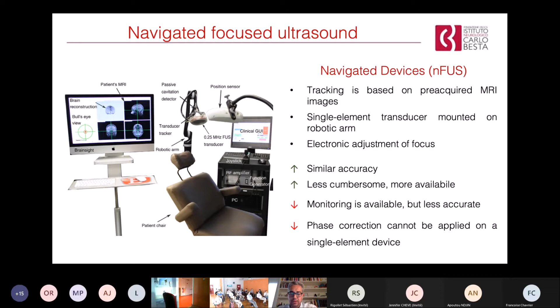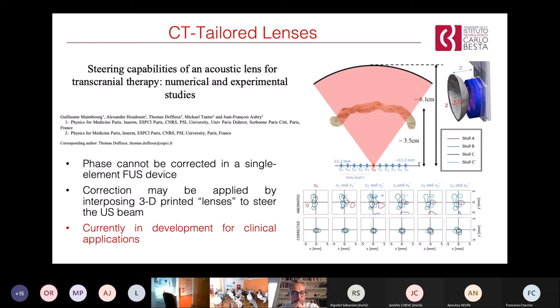There are acoustic lenses that are under development. They are built, again, on the CT data of the patient, and they are able to deform the beam before it is re-deformed by the skull, so that in the end, minus plus, the equation is 0, and the machine is able to focalize the beam correctly.